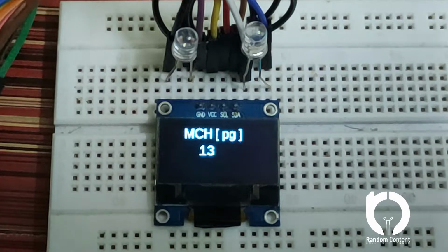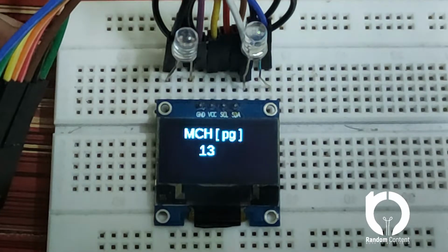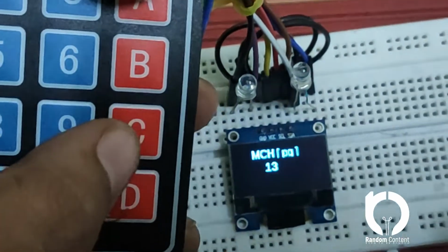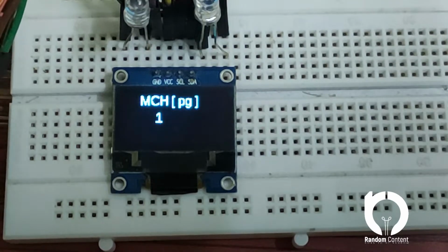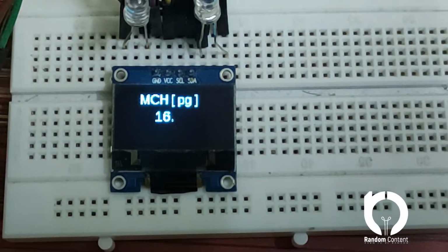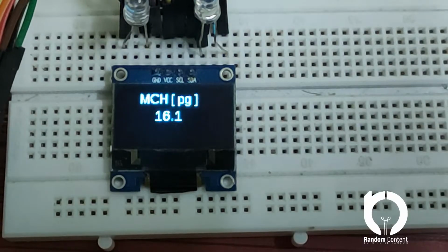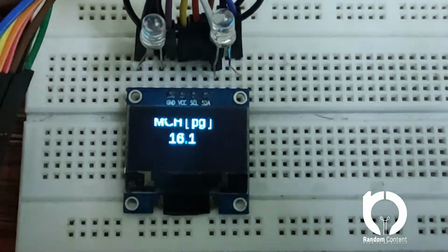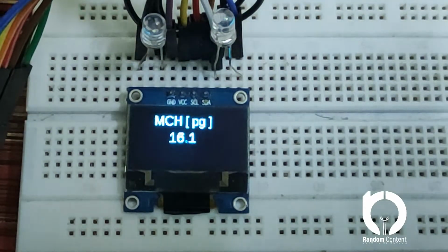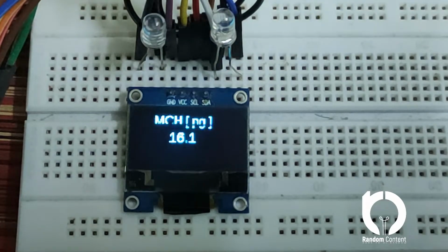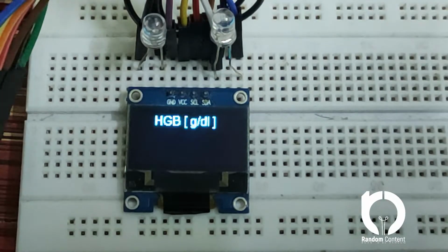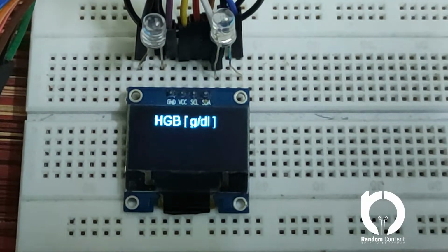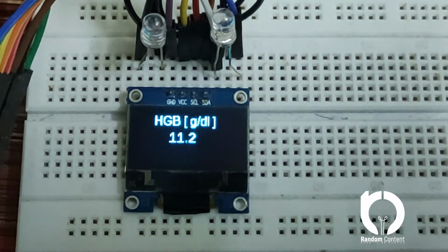16. Oh, sorry. What I can do is press the clear button, which is C here, so it will clear the value, and I can enter my proper value. I've also used the button B, which I've given the functionality to go back. If I press back, it will go to the previous value, which will be hemoglobin. The values which were entered are cleared, and now I have a chance to enter the values again.